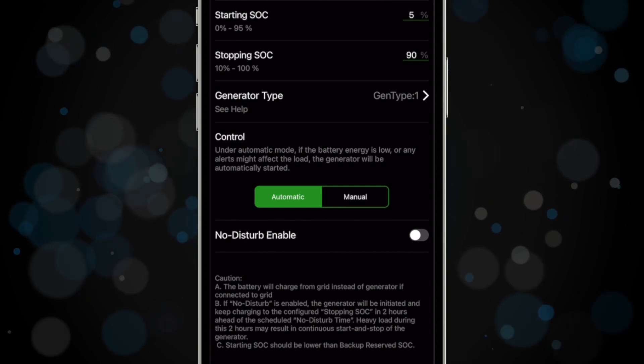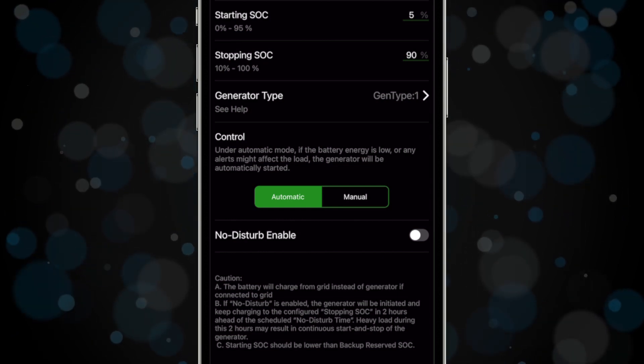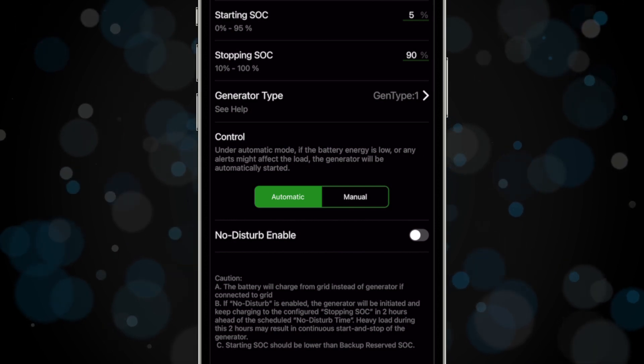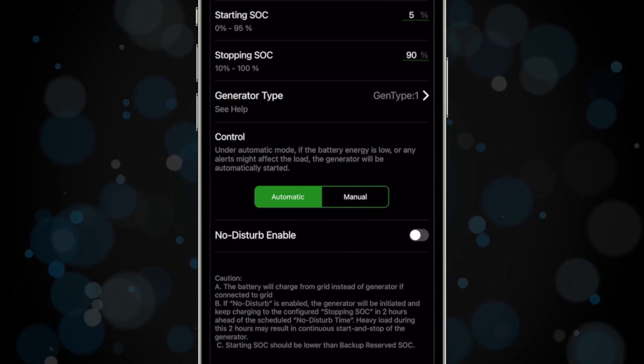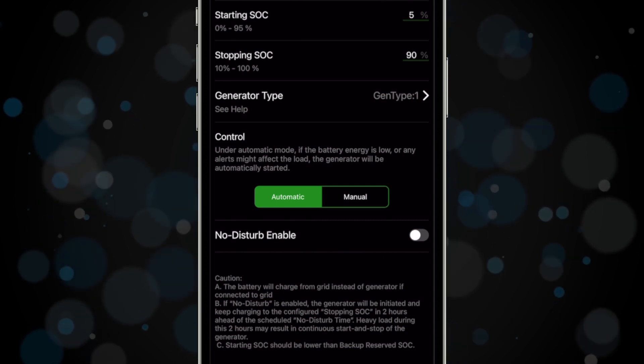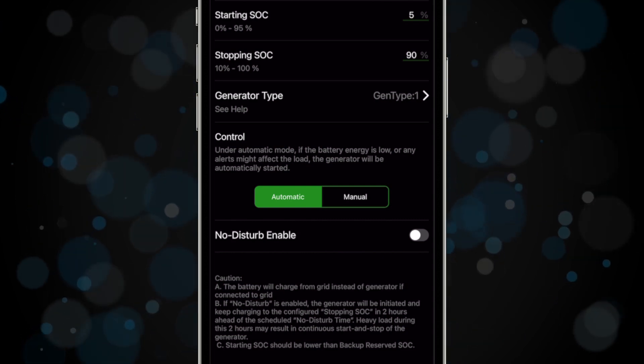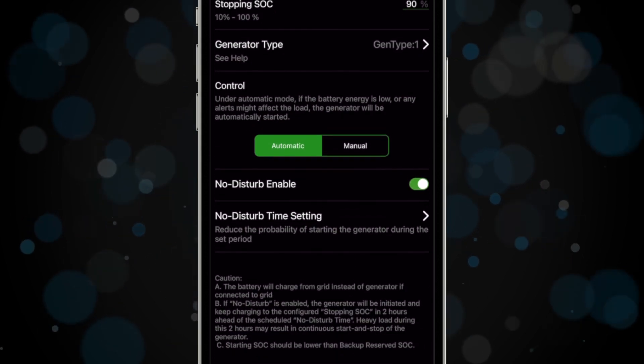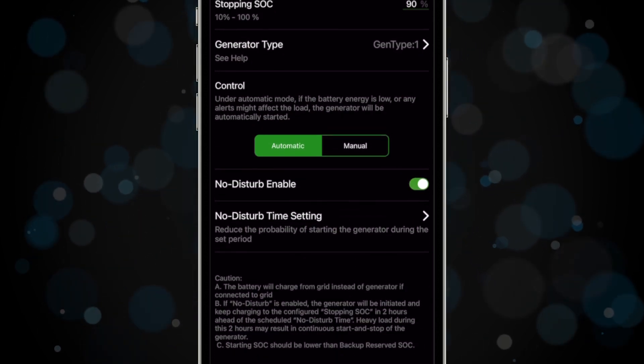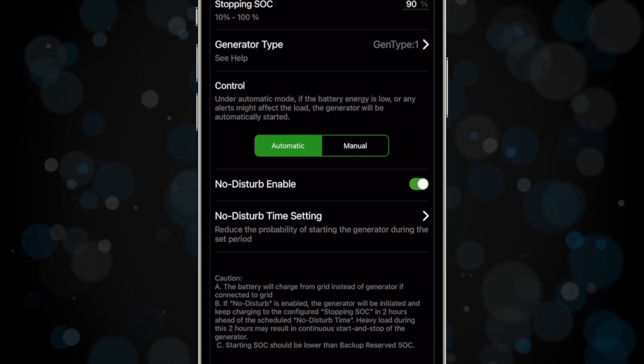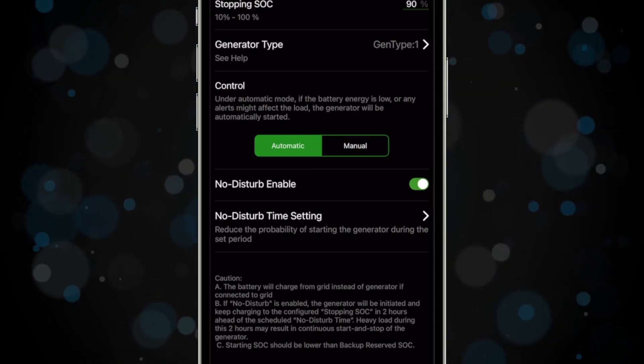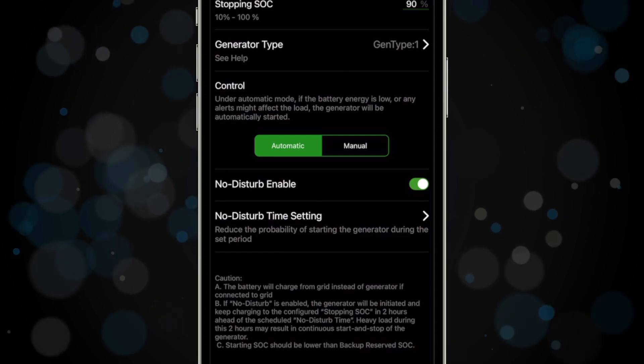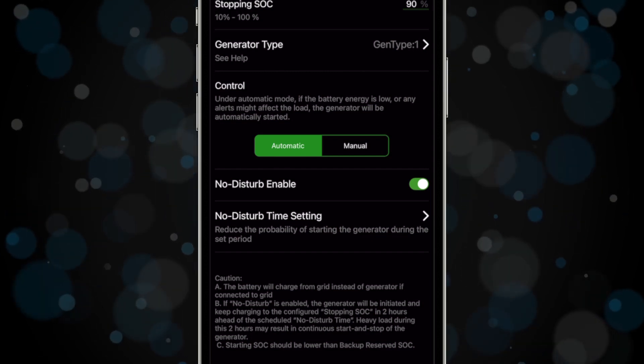If the system is connected to the grid, the generator will not turn on to charge the battery. Instead, the system will charge the battery from the grid. You can configure the No Disturb Time setting, or DND, to prohibit the generator from running during specific hours. If enabled, the generator will run more frequently in the two hours before the DND time to ensure the battery is at the stopping SOC when the DND window starts. This helps the battery last as long as possible during the DND period. Repeat these steps for all additional power inverters in the system.